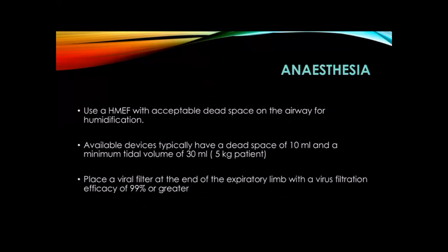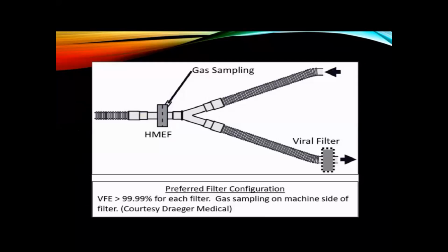Now, use an HMEF with acceptable dead space in the airway for humidification. Available devices typically have a dead space of 10 ml and a minimum tidal volume of 30 ml for a 5 kg patient. So you have to be very careful about this HME and viral filter. And place a viral filter at the end of the expiratory limb with a virus filtration efficacy of more than 99%. So this is the thing, one from the patient to the tubing, another from the expiratory limb to the machine.